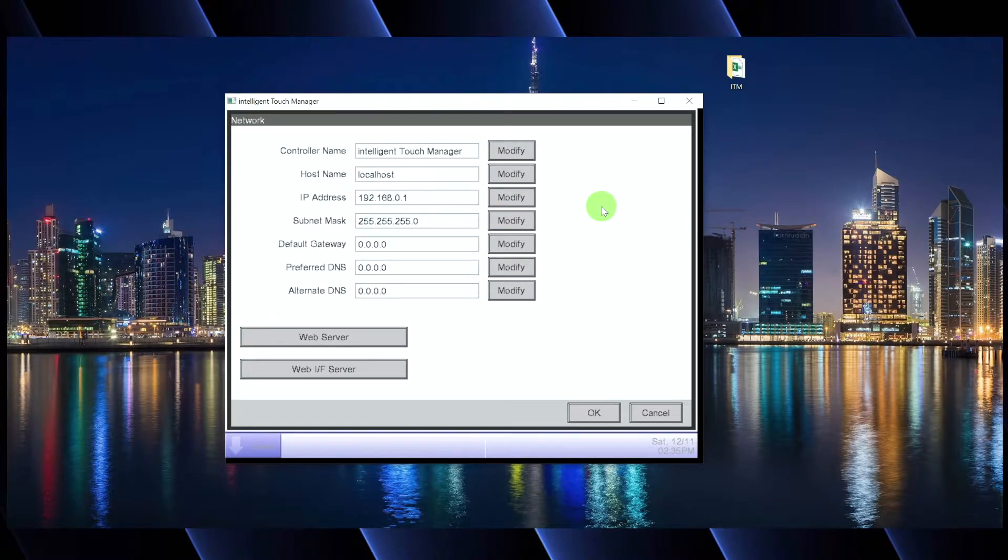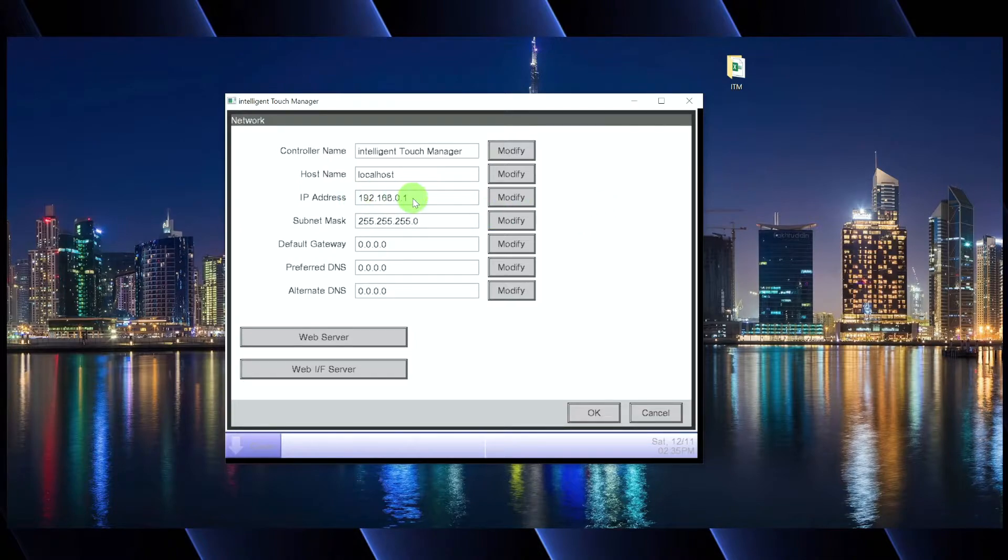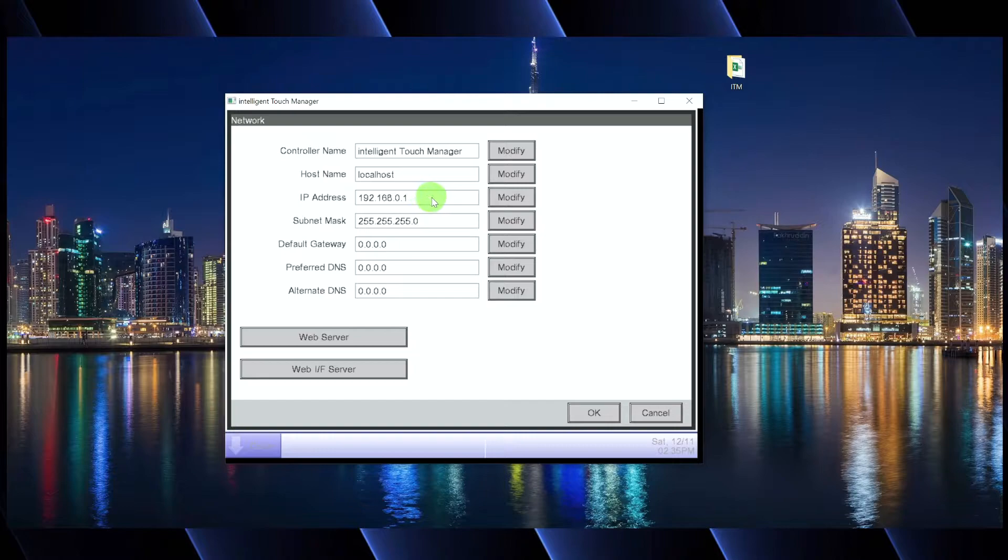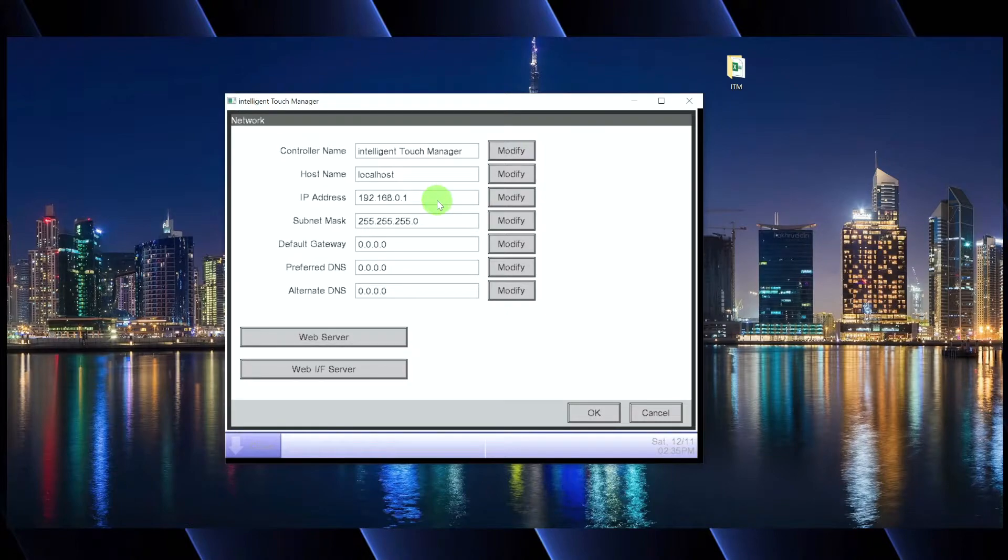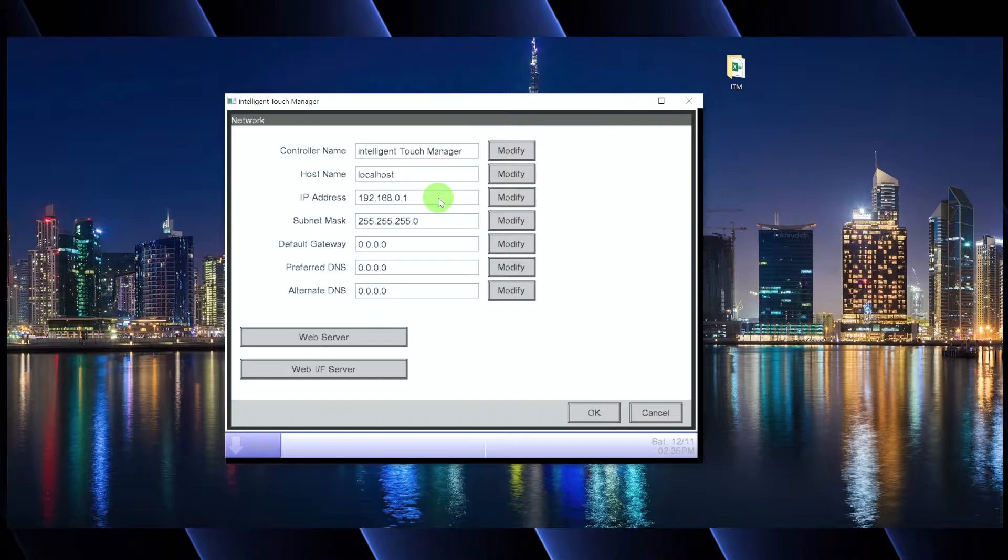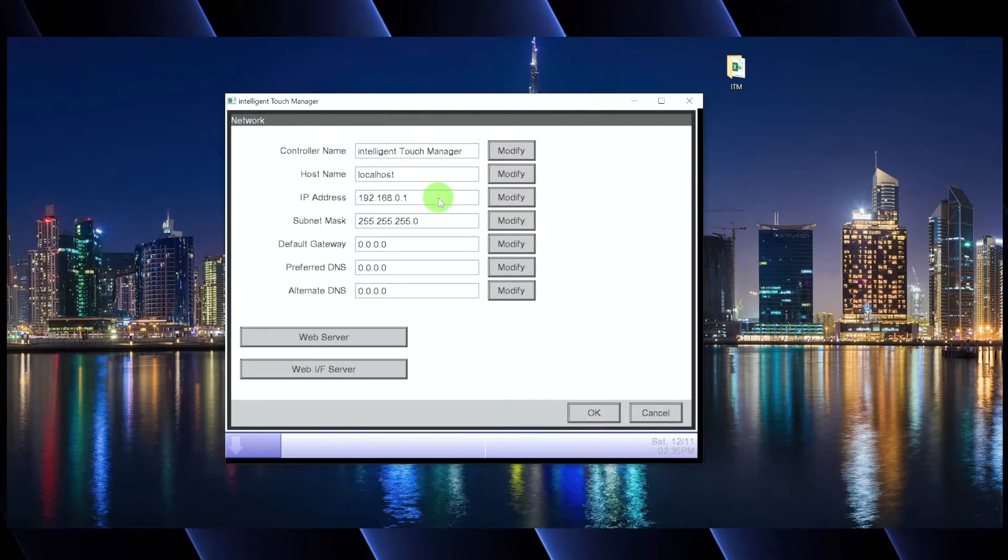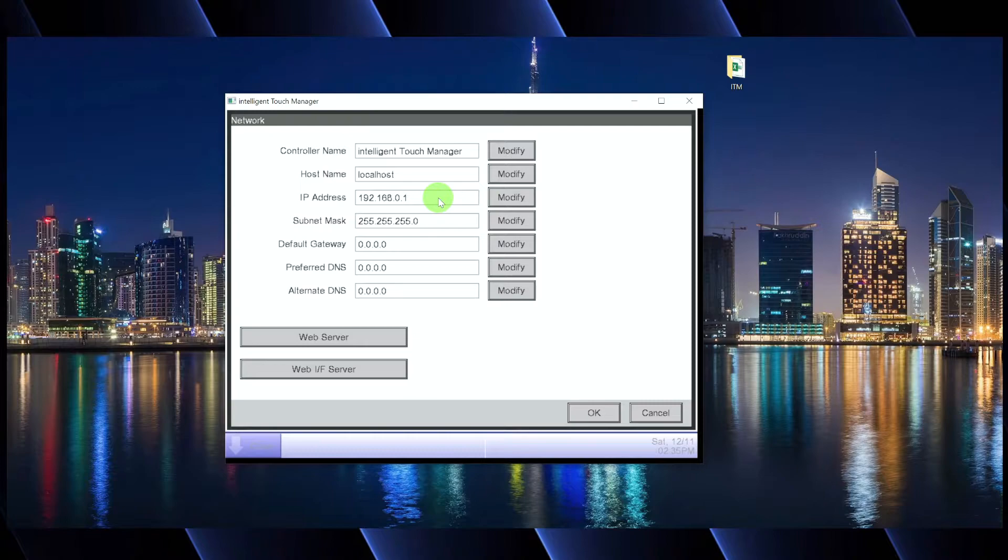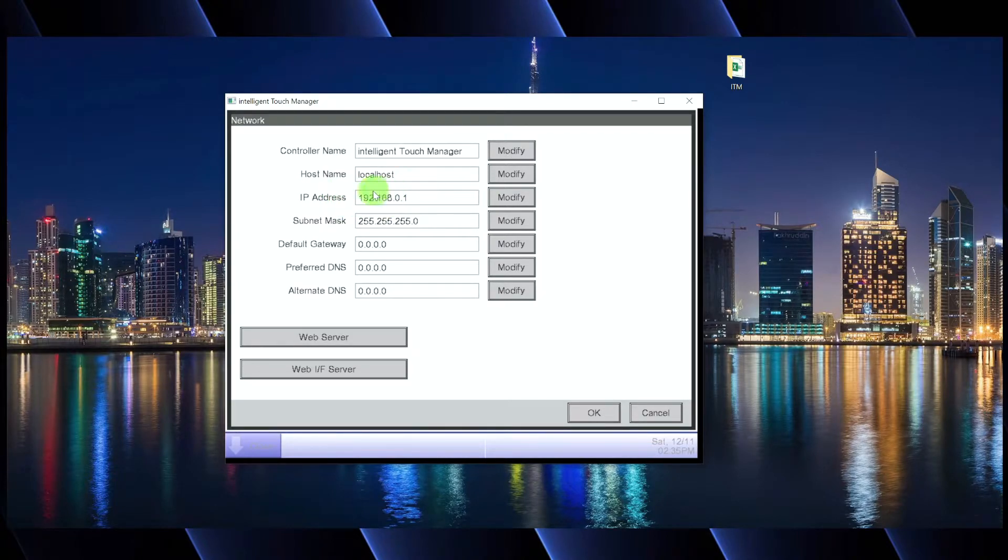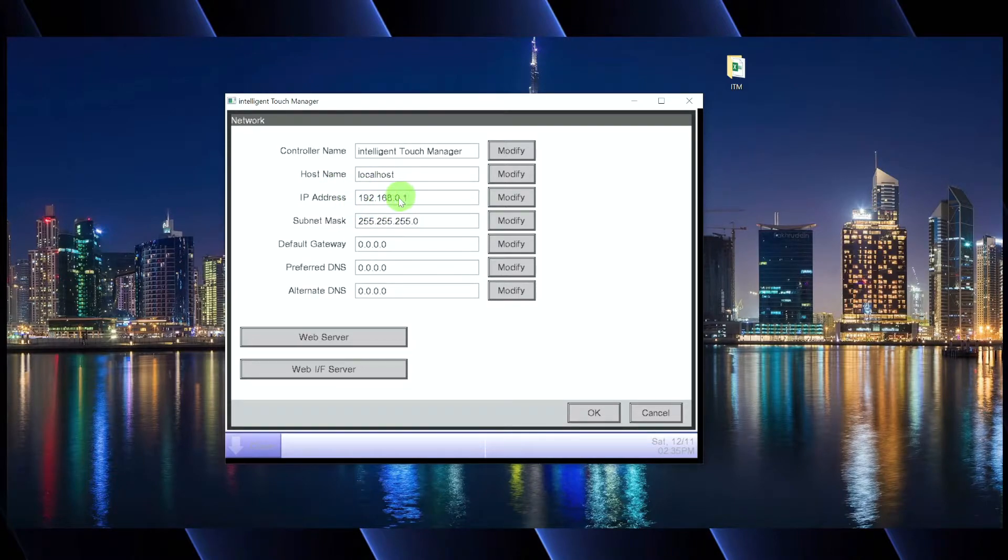Now by default, the IP address that's set up for the ITM is 192.168.0.1 and this will almost always need to be changed if you're hooking up the ITM on a local area network. So depending on your application, if you're keeping the ITM on a local network, and that is, you're not going to have any sort of remote access set up.